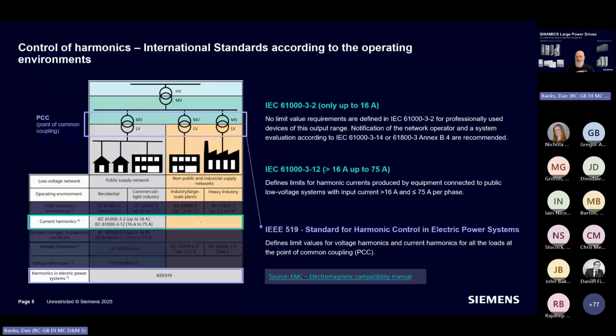What it essentially says is that the harmonic distortion on your network at the point of common coupling, where you hit the public grid, won't go above about 5%, usually 6%, or something like that. It's a long, complex standard with a lot to read about, but essentially there are several outcomes if you don't comply - ranging from your power company measuring your distortion and fining you for being over the limit, to paying based on your power factor. And if you're paying based on true power factor rather than reactive power factor, harmonics are going to factor into that.